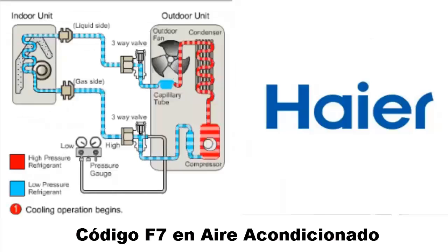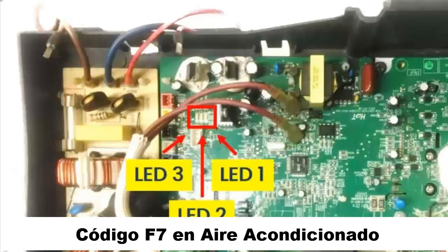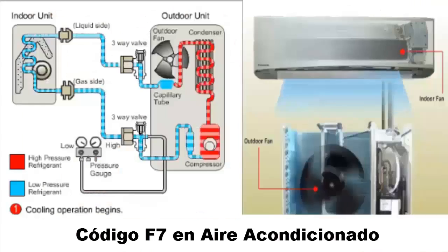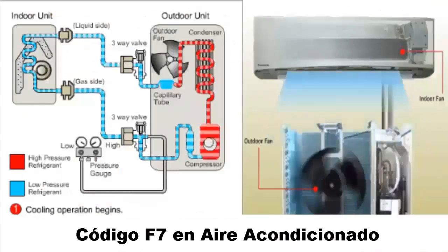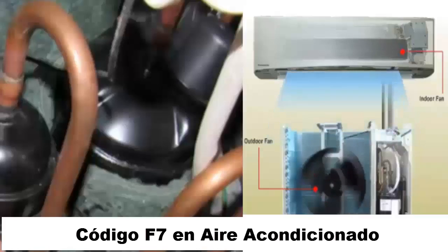You can also identify the F7 error code on a Haier DC inverter type from the outdoor unit. To do this, observe when LED 1 on the outdoor unit's board flashes, indicating that this error code is displayed on the screen. It will flash 11 times on the outdoor unit, which means they have the same meaning. This indicates that the outdoor PCB has a fault when the suction pipe temperature sensor is open or short-circuited, showing F7 on the screen.